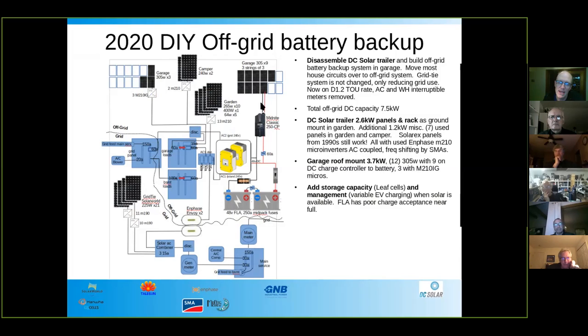I also need to change settings in the Sunny Island inverters so that during the day it charges the batteries as much as possible — opening up the charge limit so it accepts everything the panels can produce. But at night, if it hasn't been sunny and the state of charge is low, I want it to connect to the grid and supply the house loads without charging the batteries. The only way to do that is to set the battery charge limit low, to 10 amps, so it just barely charges overnight.